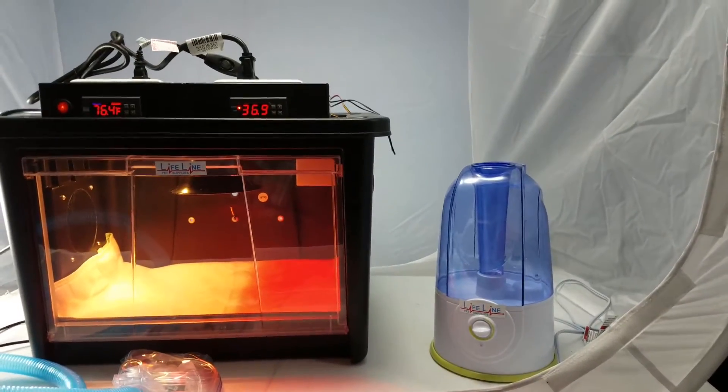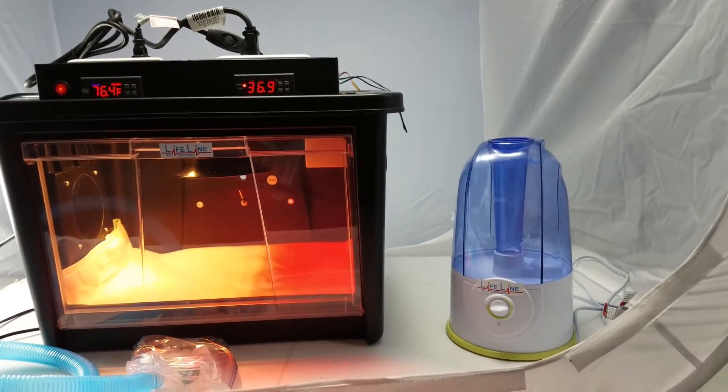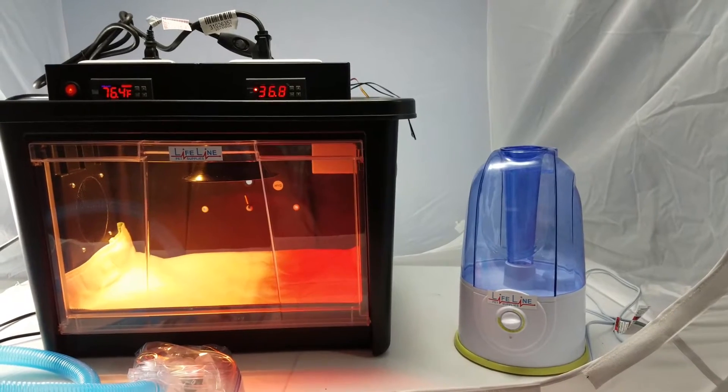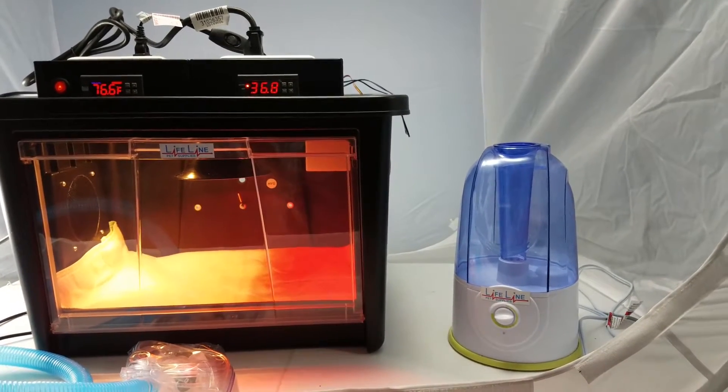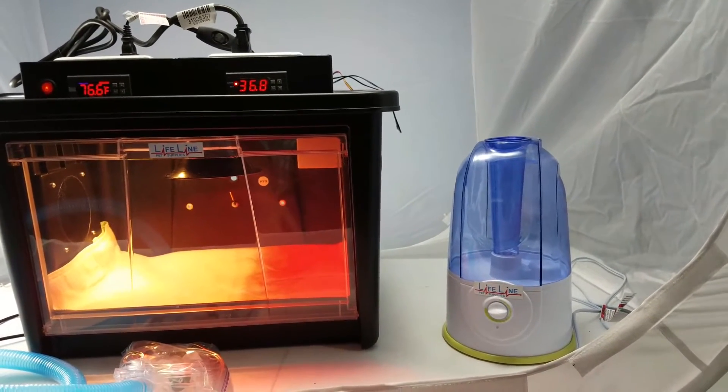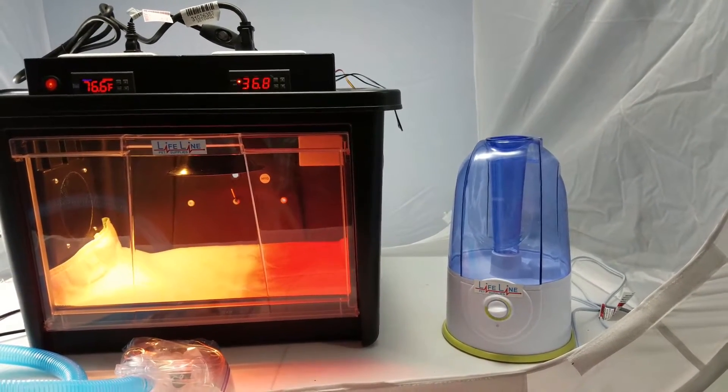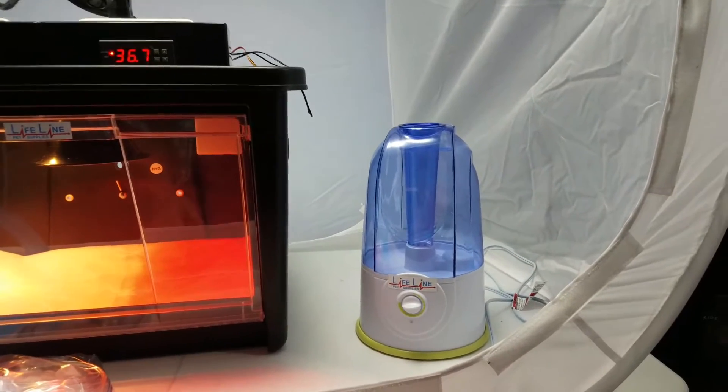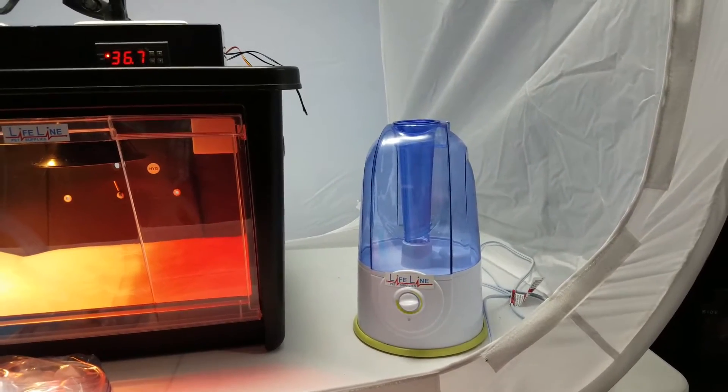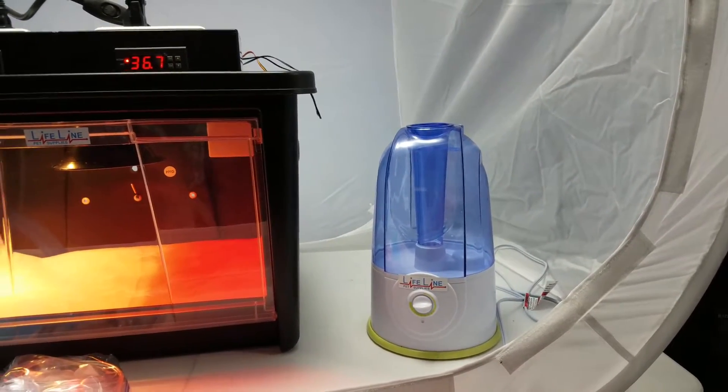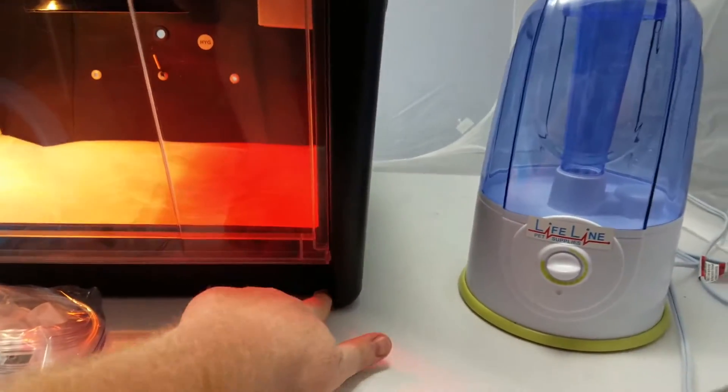So this is pretty easy to set up. You just kind of need to follow the procedure step-by-step. One important thing to note is that the humidity pump, the top of the pump, needs to sit lower than the bottom of the incubator.